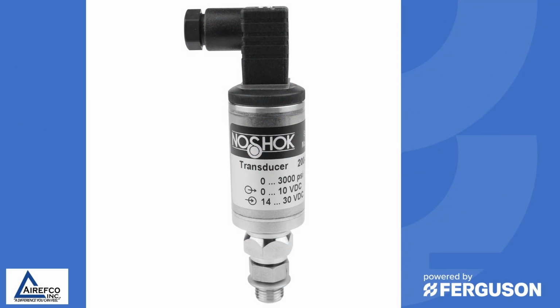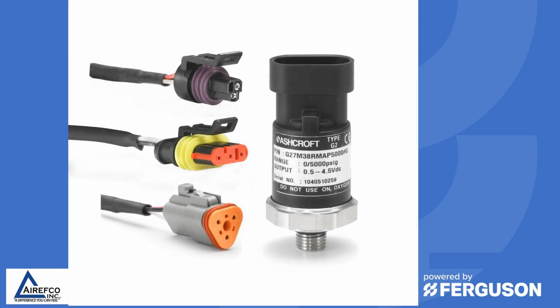In this video, we're going to talk about transducers. Transducers have been used for many years on chillers and larger equipment, but now with the inverters getting into the residential market, you're seeing transducers being used on residential heat pumps and air conditioners. So a transducer is a device that screws onto the high side or the low side of a system and translates pressure into a DC voltage signal that tells the board what the pressure is that the transducer is reading.